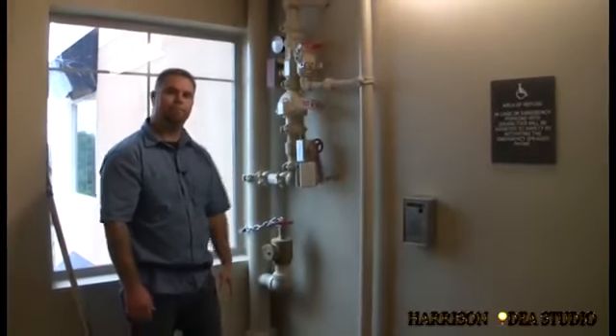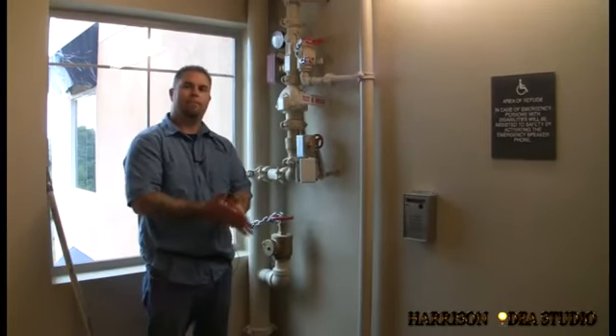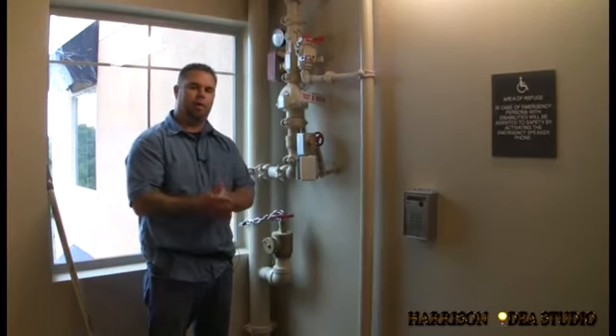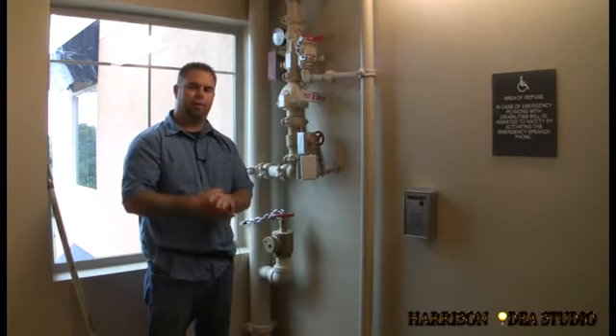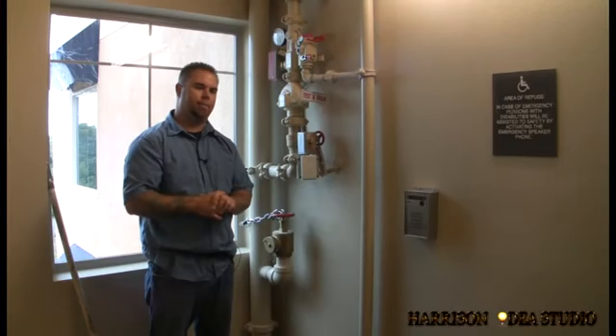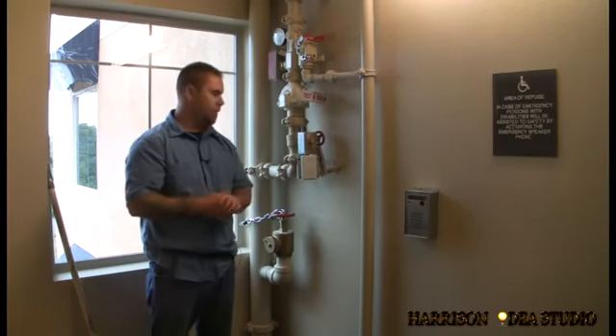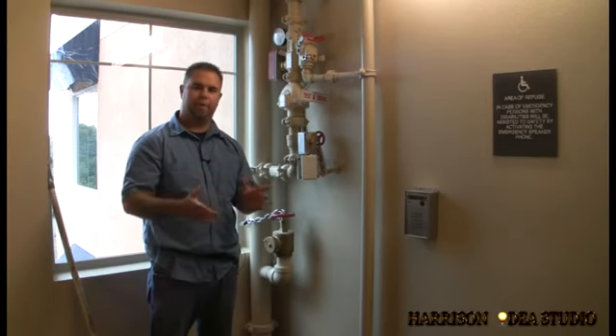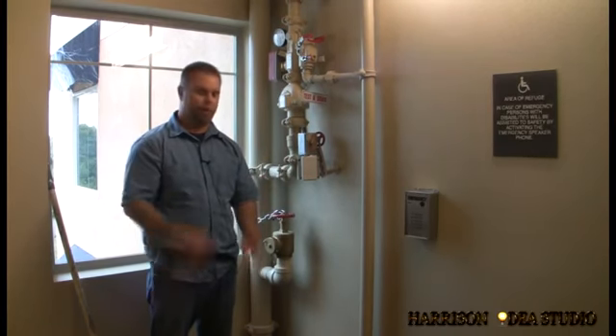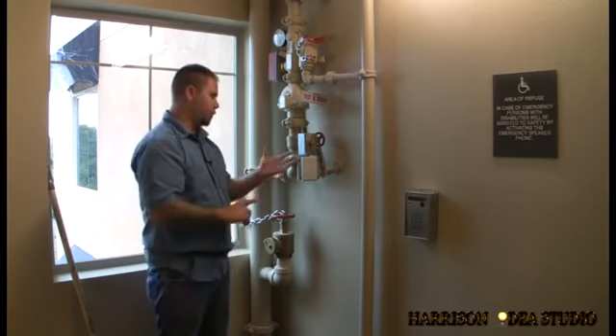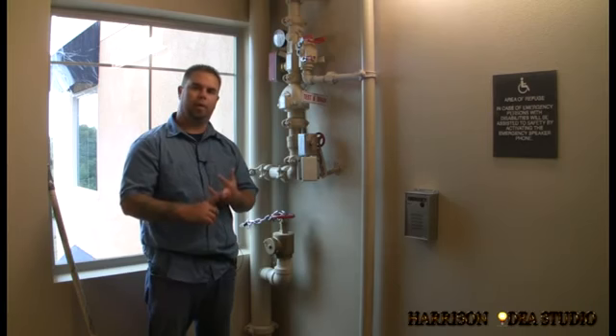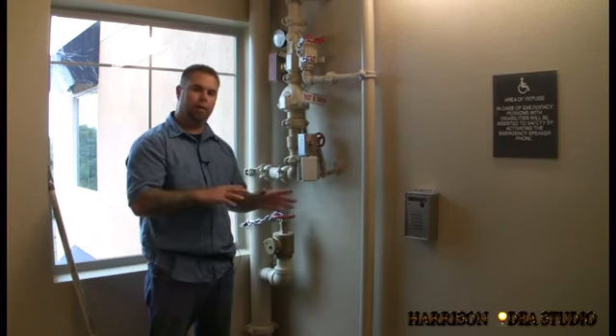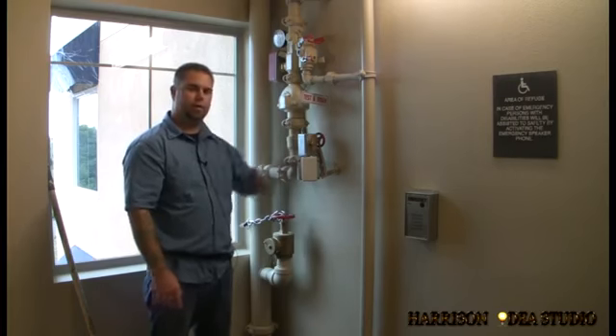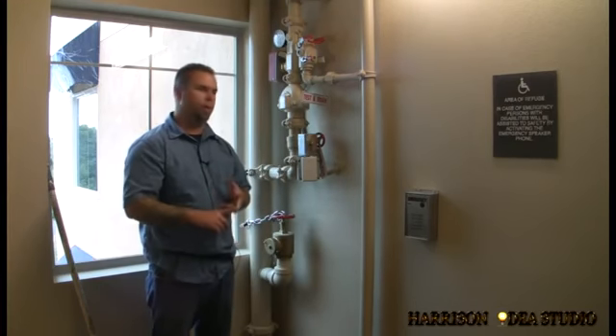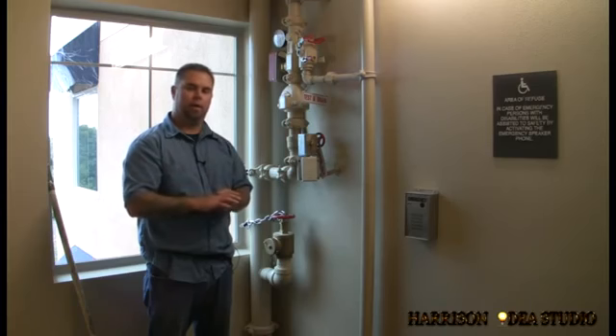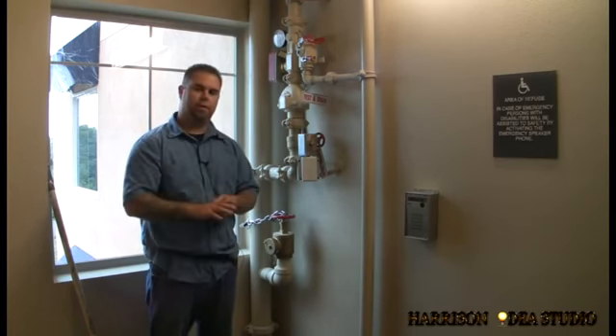Is there a state dictated schedule for testing these systems? Yes, there are annual inspections and 5-year inspections. Each one of those entails different items to be inspected and or tested and or serviced. Your annual inspection has your control valves we service and make sure that they are in operating condition, and the alarm panel is monitoring all the devices. Your 5-year inspection gets more in detail with inspection of piping and hangers and all the rest of the devices in the system.